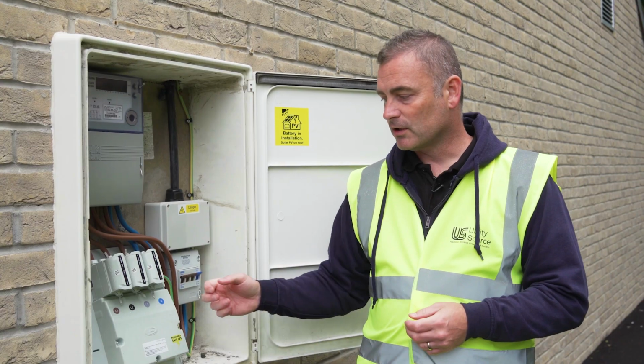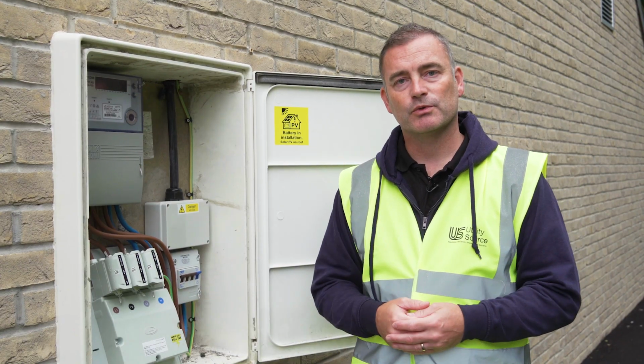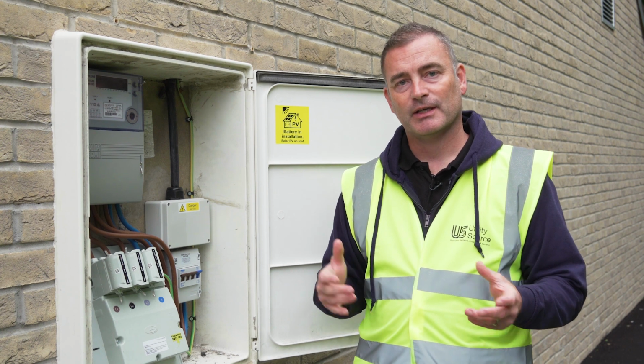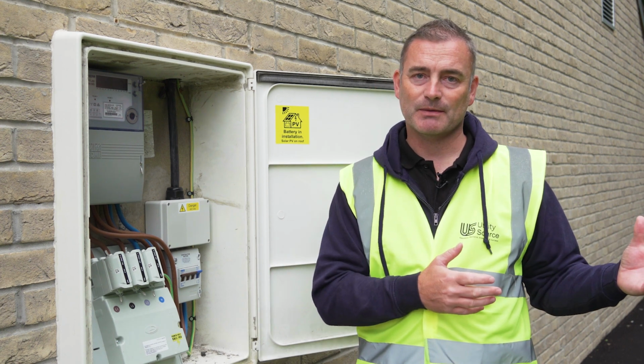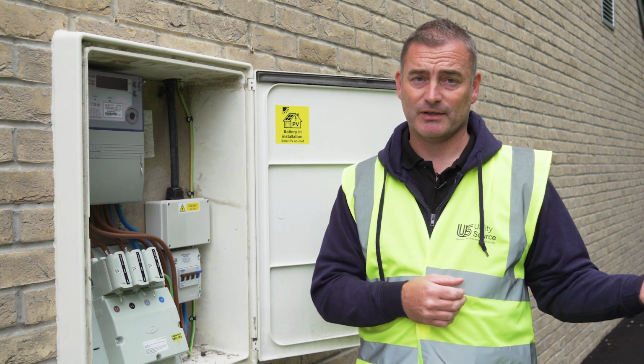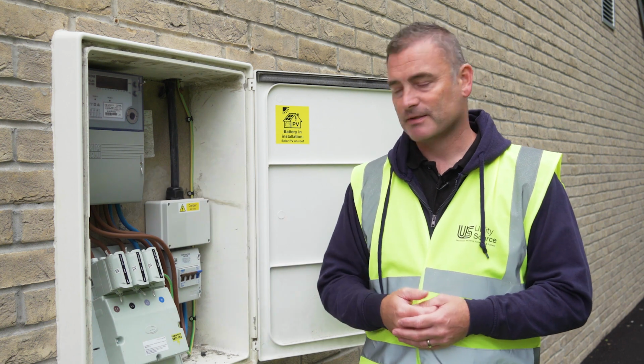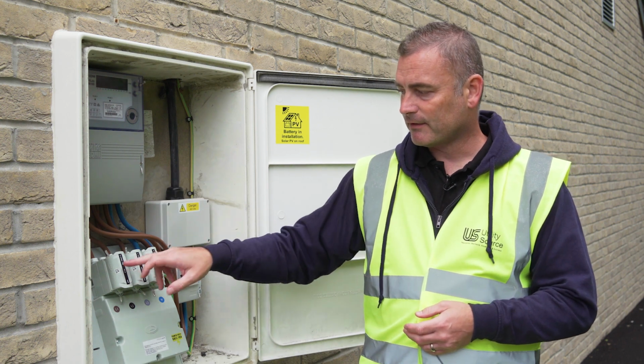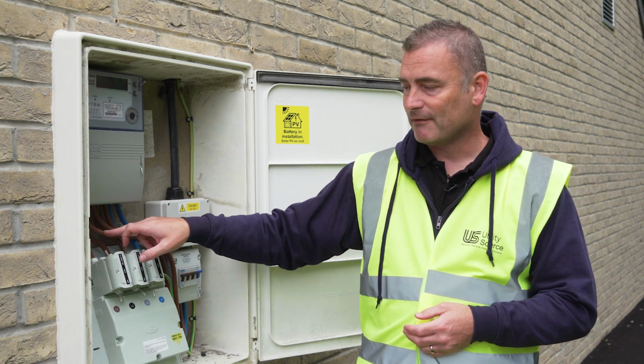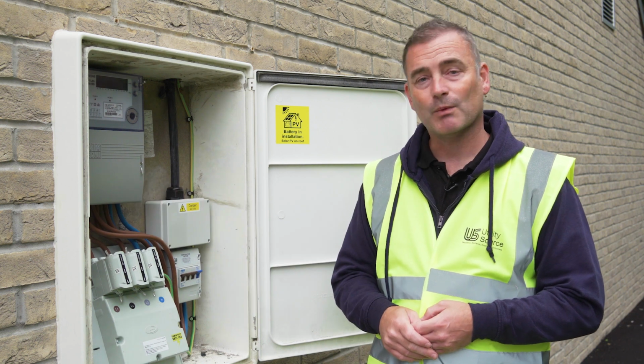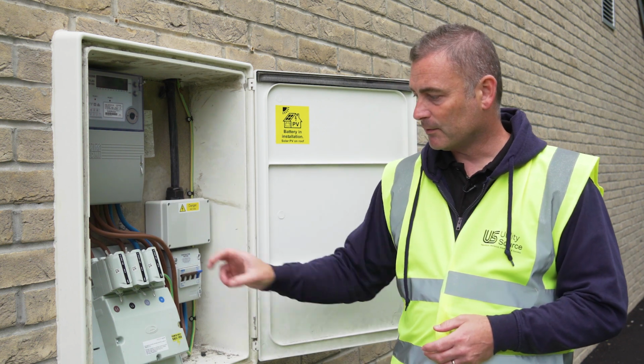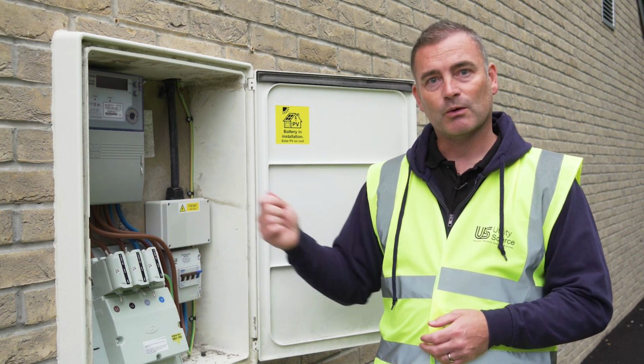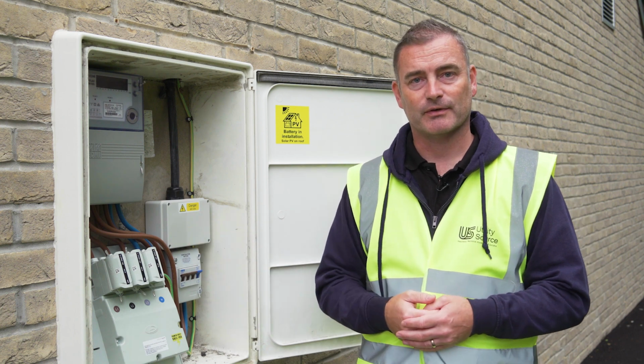When installing a three-phase supply, it's important to understand that the meter is different to that of a domestic property. So instead of having a single phase meter, we have a three-phase meter, and you can see coming out of the three fuses is the wiring that comes into the three-phase meter. So you've got wiring on each phase. If you were to take a fuse out, you isolate one phase of the three phases, for example.